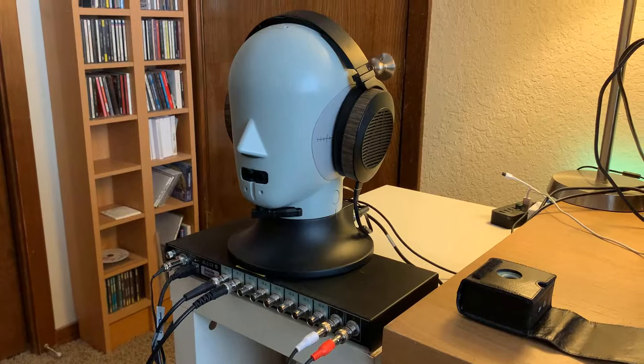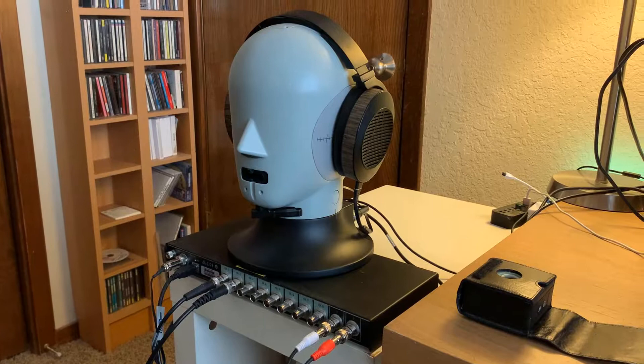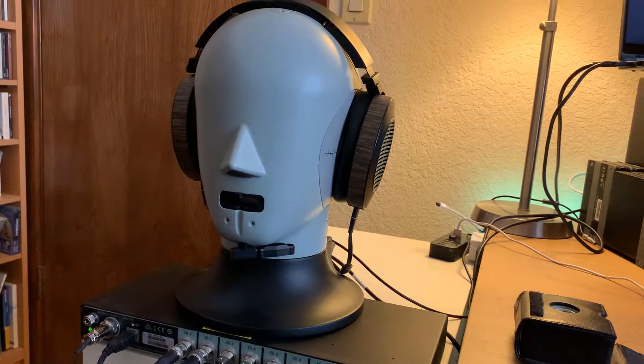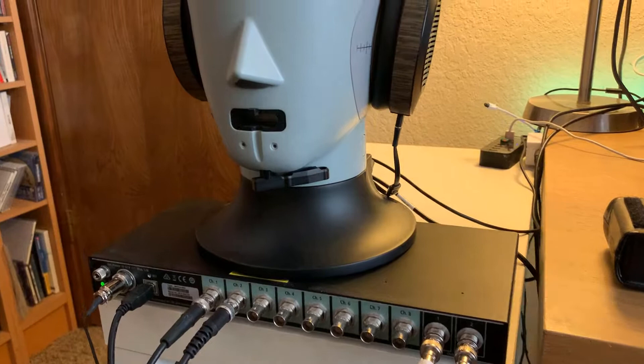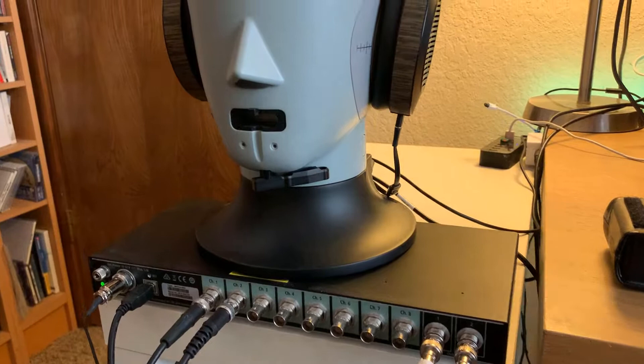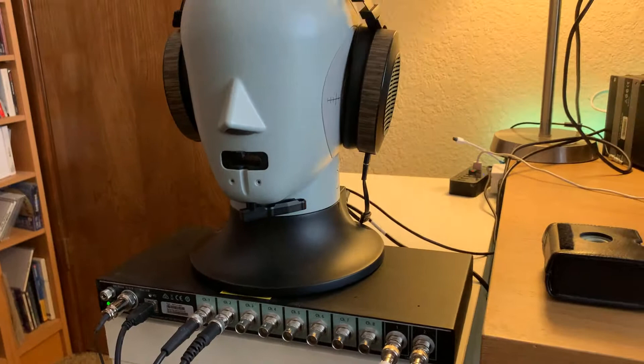I'd like to give a more substantial demo of the EA Engine using the head simulator type 5128. It has a mouth so it can talk, and two high-frequency artificial ears so it can listen and measure headphones. The headphone is connected to outputs 1 and 2, and the ears are connected to inputs 1 and 2 of the 3670. This is a simple 2-in 2-out test.